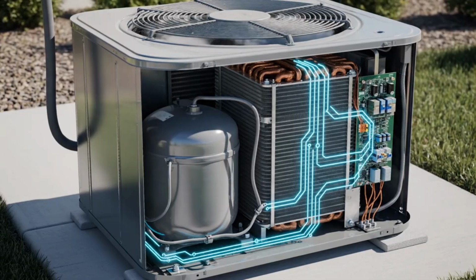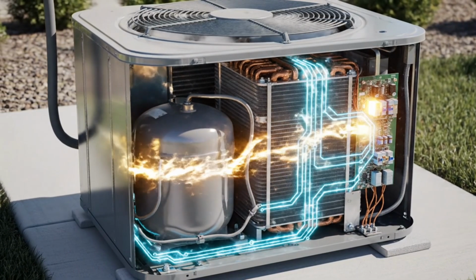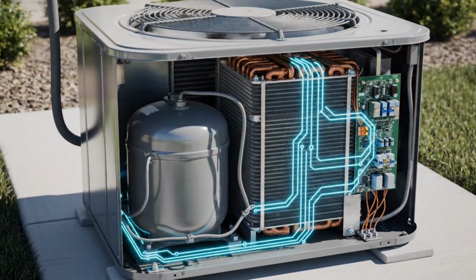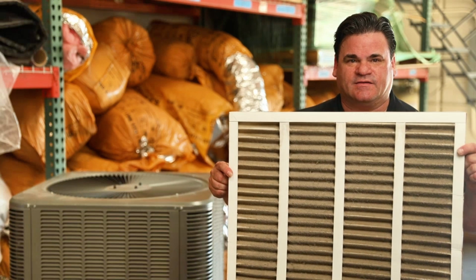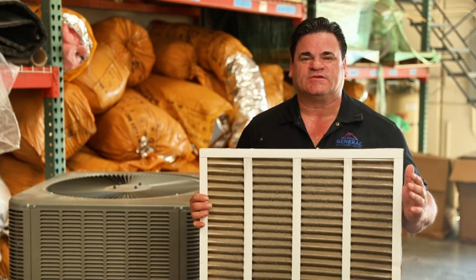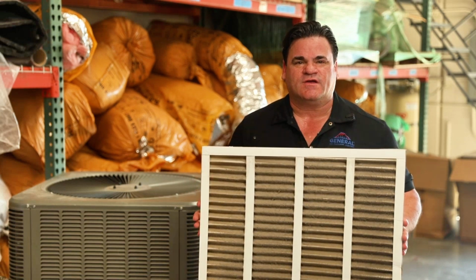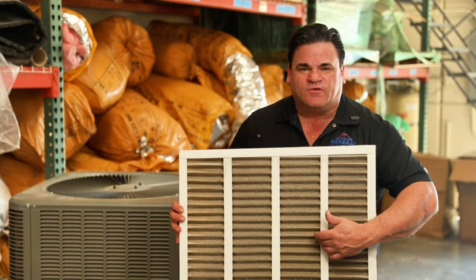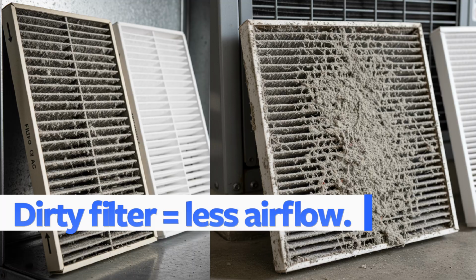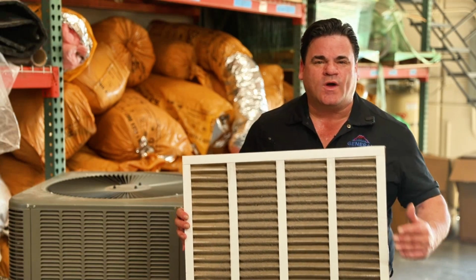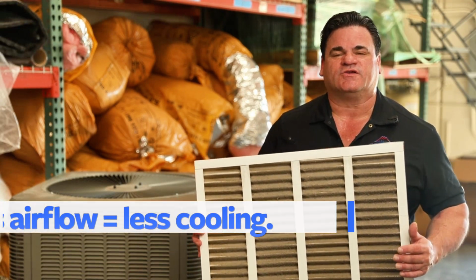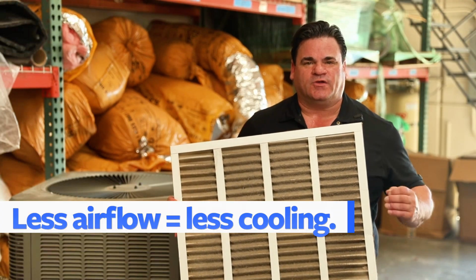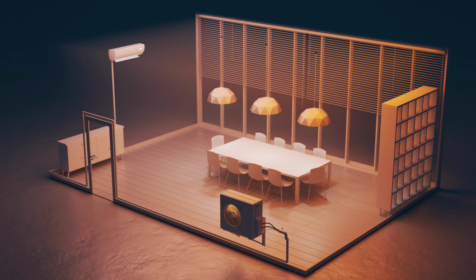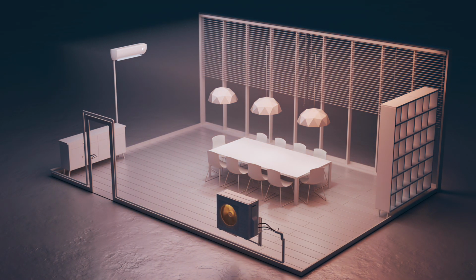Next, now if your system is operating, but it seems to struggle to cool, it's not cooling as quickly as it normally does, or it's just not getting down to the right temperature, check your filter. Again, the filter is super neglected. We go out to homes where we have systems that all we do is change a 1-inch filter and the system performs as it should. Once you get to a 50% buildup on this filter, it can dramatically impact your system. As little as a 20% buildup is going to start having an impact on your system and decreasing its efficiency and ability to cool. And the higher the temperatures are out there, the harder your system's going to work and the bigger the impact is going to have on it.